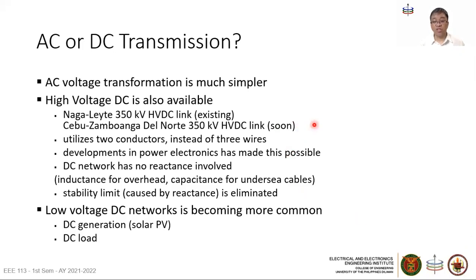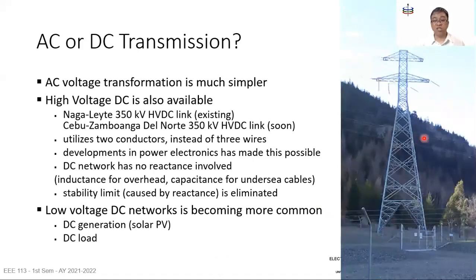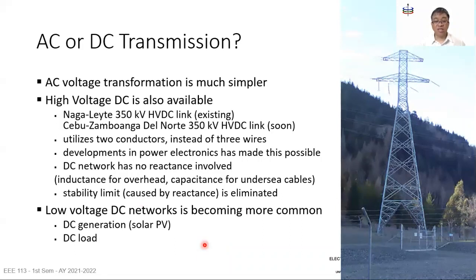Instead of three conductors, HVDC only needs two conductors. Reactance is eliminated and some stability issues are eliminated as well. Towers for high voltage DC look different — they don't have a set of three wires but just a pair of wires, with the others being pilot and communication wires. Low voltage DC networks are also becoming more common because DC generation such as solar PV, and DC loads for electronics and equipment, are much more common these days.